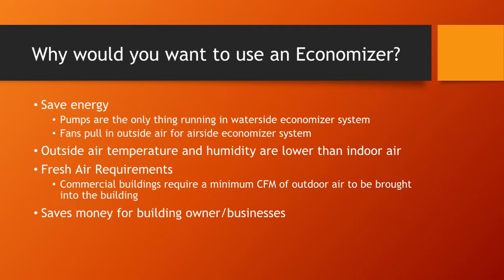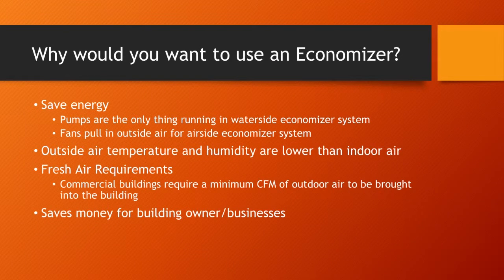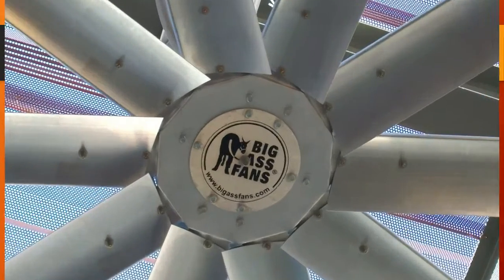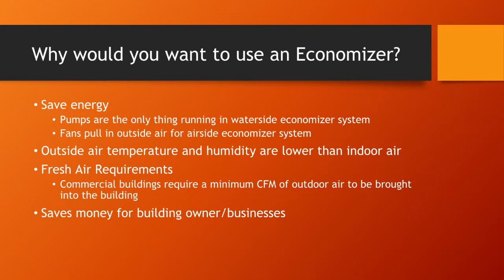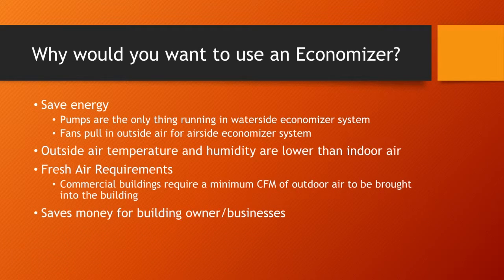Alright, so why are you going to want to use an economizer on your system? It's going to save energy. You're only going to be using pumps to circulate water on that water side economizer, and you're only going to be using fans to pull in that outdoor air for your air side. Outdoor air temperature and humidity are lower than indoor air, so depending on where you're at, if you're in like a northwest region, it's going to make sense to use that outdoor air.